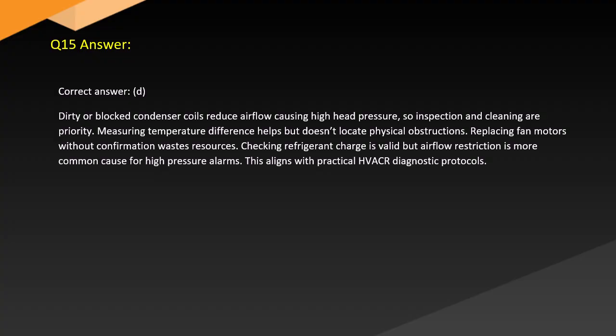Answer. Correct answer: D. Dirty or blocked condenser coils reduce airflow, causing high head pressure, so inspection and cleaning are priority. Measuring temperature difference helps but doesn't locate physical obstructions. Replacing fan motors without confirmation wastes resources. Checking refrigerant charge is valid, but airflow restriction is the more common cause for high pressure alarms. This aligns with practical HVACR diagnostic protocols.